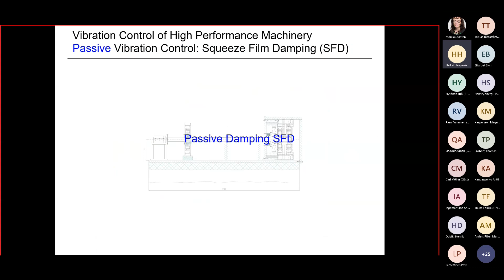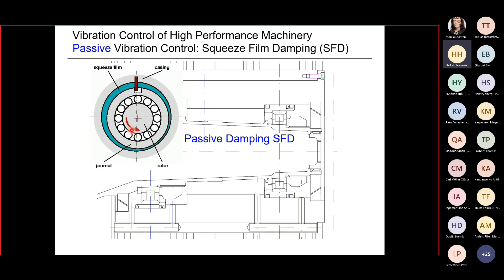I will show how we can realize passive damping by means of squeeze film dampers. They are located here between these bearings and the housing. The idea is that with this passive damping, we have the outer ring of the bearing and the casing, and between them there's the oil film. If there are vibrations, then the oil film is squeezed.